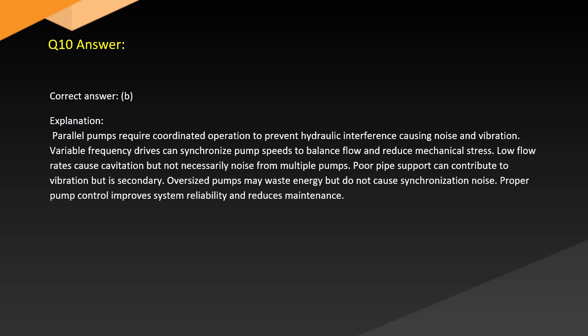Answer. Correct answer: B. Explanation. Parallel pumps require coordinated operation to prevent hydraulic interference causing noise and vibration. Variable frequency drives can synchronize pump speeds to balance flow and reduce mechanical stress. Low flow rates cause cavitation but not necessarily noise from multiple pumps. Poor pipe support can contribute to vibration but is secondary. Oversized pumps may waste energy but do not cause synchronization noise. Proper pump control improves system reliability and reduces maintenance.